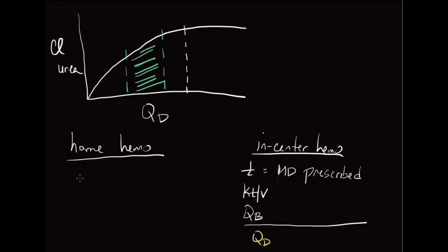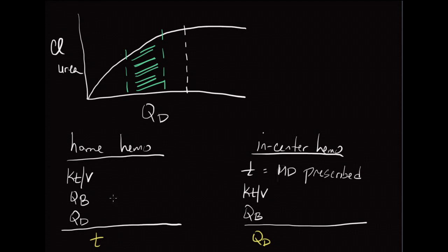That's not what happens in the home hemo patient. For home hemo, we tell the machine what KT/V we want, what blood flow we want for the same reasons as in-center, and what dialysate flow we want — because we're limited by how much dialysate volume the patient can store at home. The machine then tells us how much time it will take per session. We aim for a dialysate flow rate that gives the most urea clearance — the best KT/V — because that gives us the least amount of time on the dialysis machine. To do all that, we look at the flow fraction.